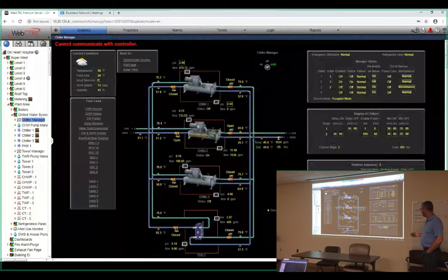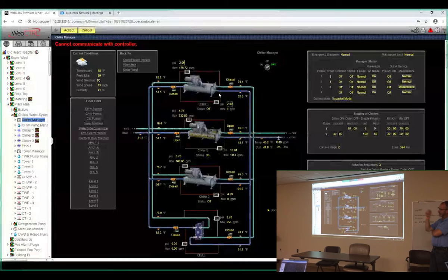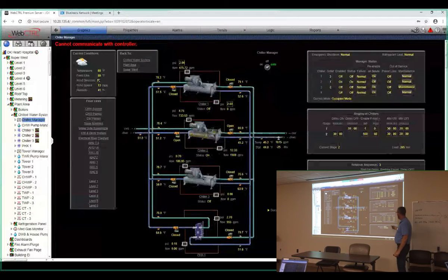All right, rotation methods. Go ahead and just click that drop down there. We have 5 different rotation methods that you can run on. Right now I've got it set to manual rotation. I've got to click it or accept a rotation. But you can choose to rotate daily, weekly, monthly, or based on the runtime of your primary chiller. So go ahead and select weekly. Get an OK or accept for me. This graphic will change here in just a second.